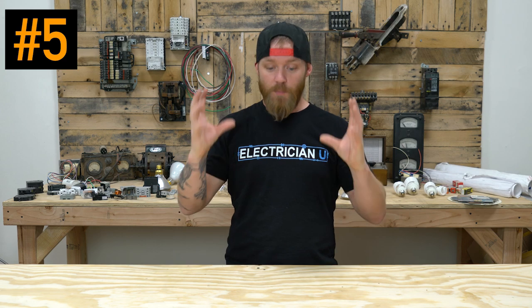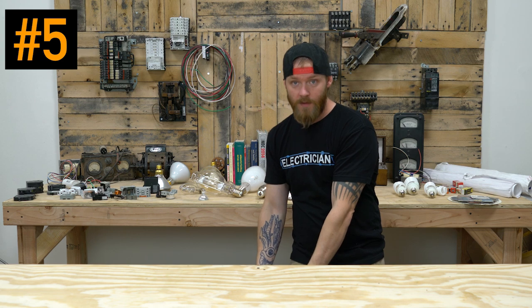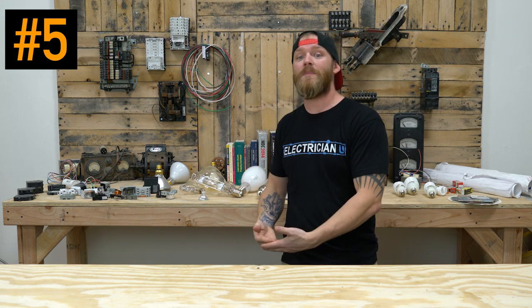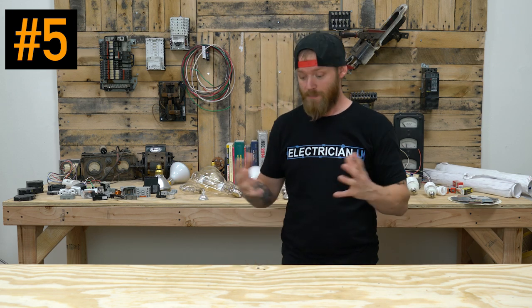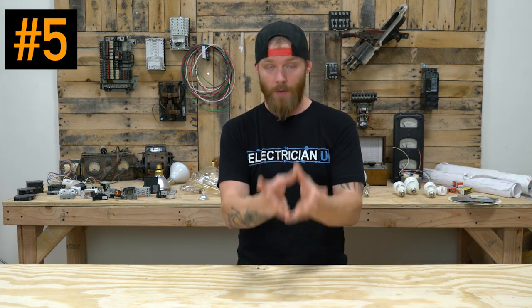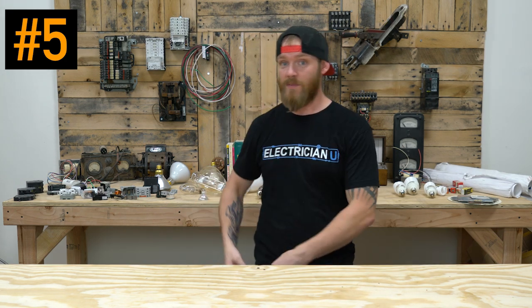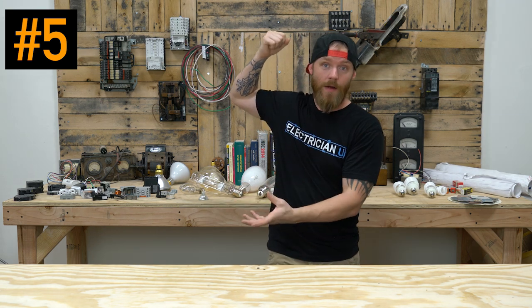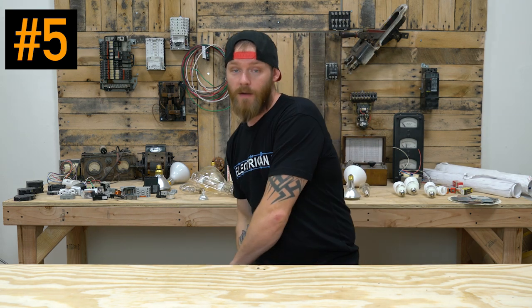Number five is grounding electrode. A grounding electrode is a purposeful piece of conducting material that is installed into the ground to establish an equipotential bond, essentially, with the ground. It's bringing the earth to the same potential as the grounding conductors and the grounded conductor that are in the service. So a lot of times, some people will put a ground rod. They'll hammer that thing into the ground and they'll bring a conductor from it and put it up into the service panel. And that brings the earth's potential to the same as the equipment grounding conductors and the grounded conductor or the neutral.